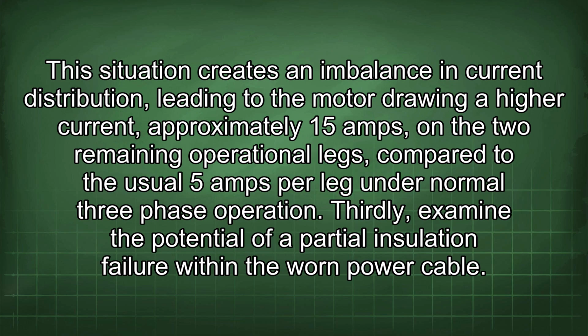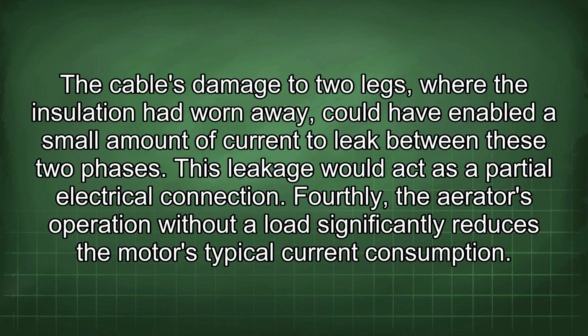Thirdly, examine the potential of a partial insulation failure within the worn power cable. The cable's damage to 2 legs, where the insulation had worn away, could have enabled a small amount of current to leak between these 2 phases. This leakage would act as a partial electrical connection.